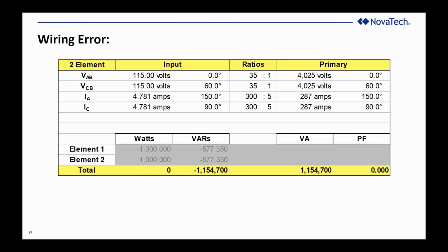So if I was to reverse one of the phases and it showed the right number with a negative sign, that would be the wrong phase. If it shows the right number with the right sign, that would be the right phase, and it would have corrected the problem. And that's all the indication you're going to get on a 2-element wattmeter.